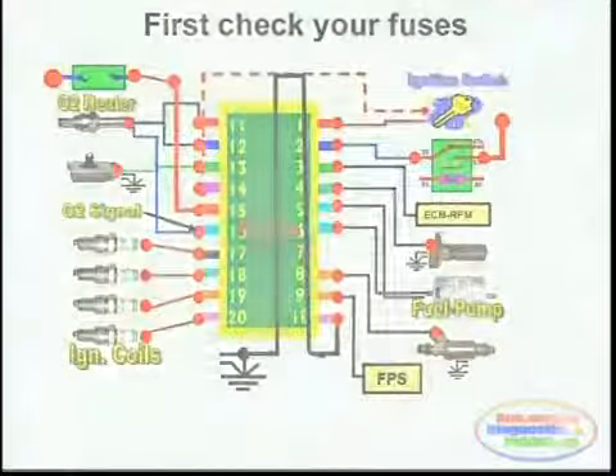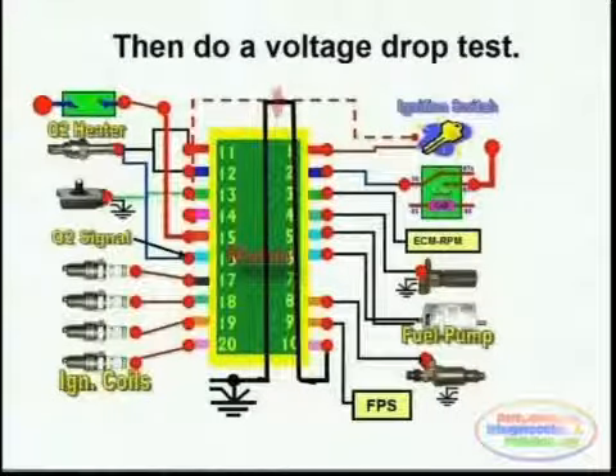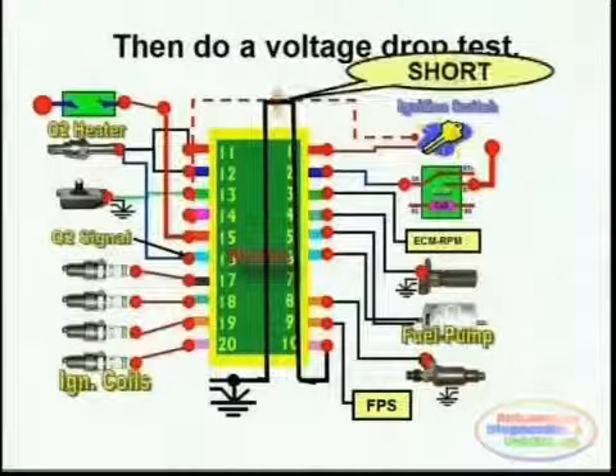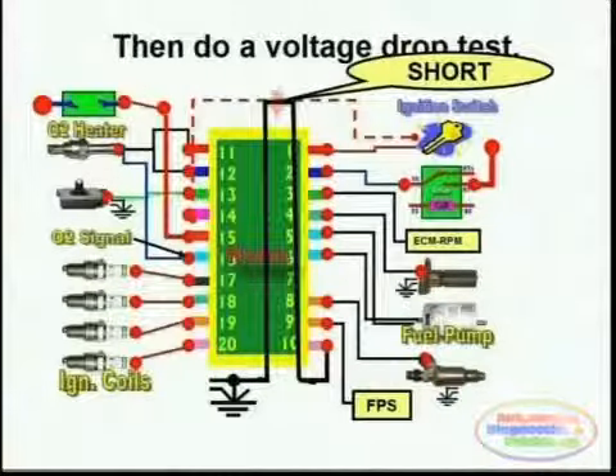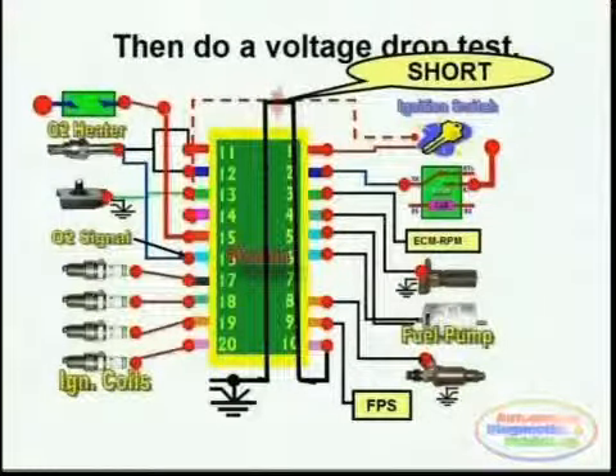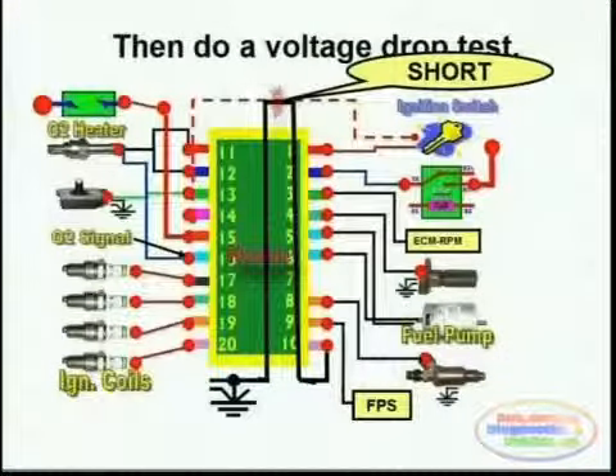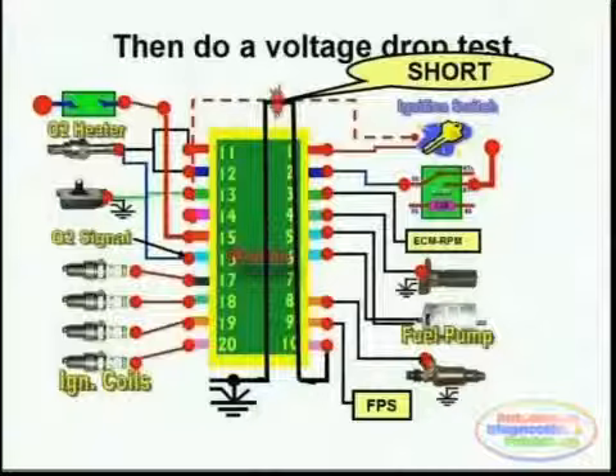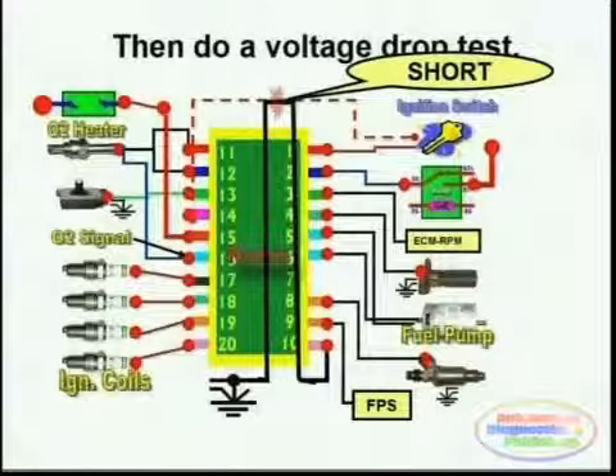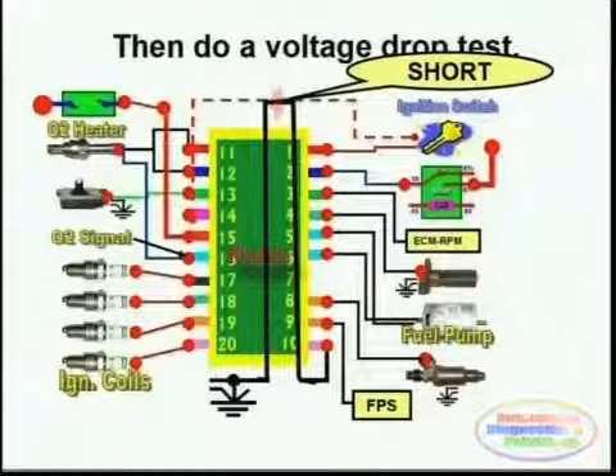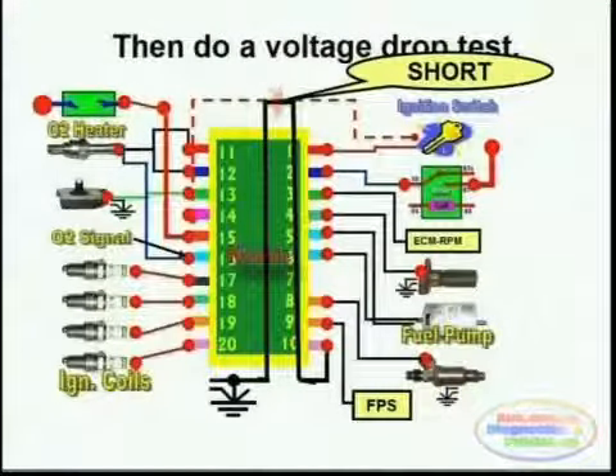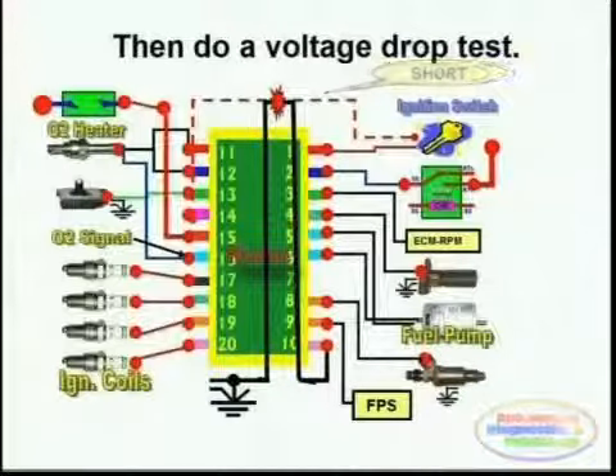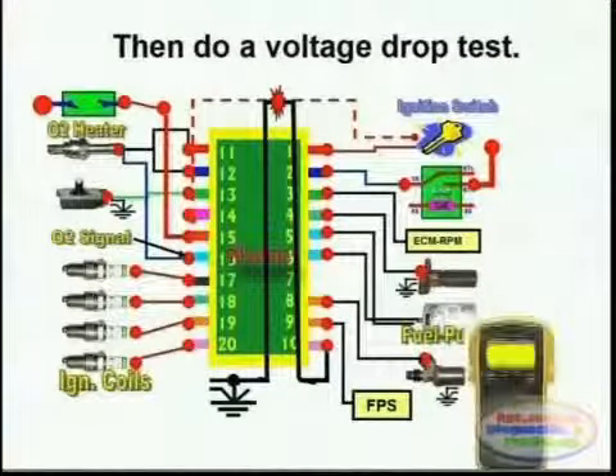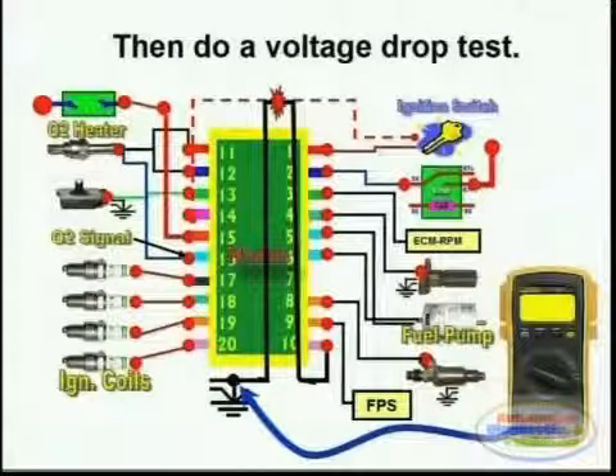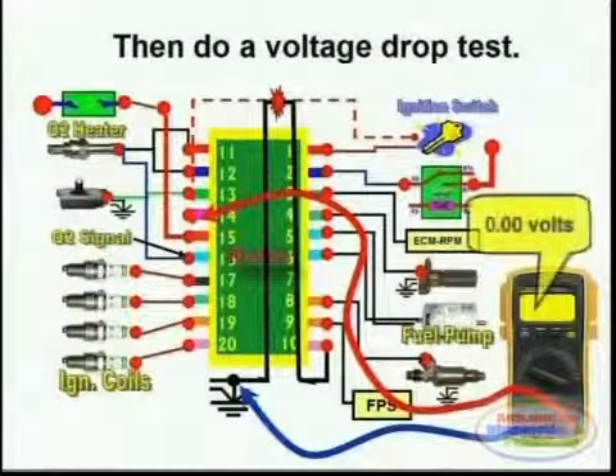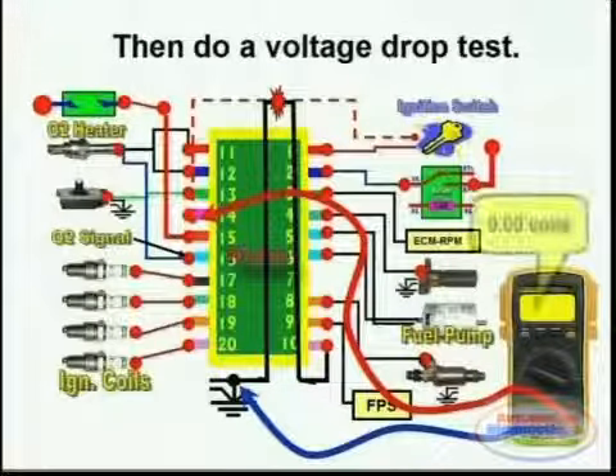In our next example of a short circuit, we see how the ground line is actually touching the ignition side of the ignition feed to the ECM. This will cause the fuse to pop, but even if it doesn't pop, you will still have a shorted voltage supply source. By performing a voltage reading across pins number 14 and chassis ground, you are supposed to have 12 volts, since this is the switch side going into the module.